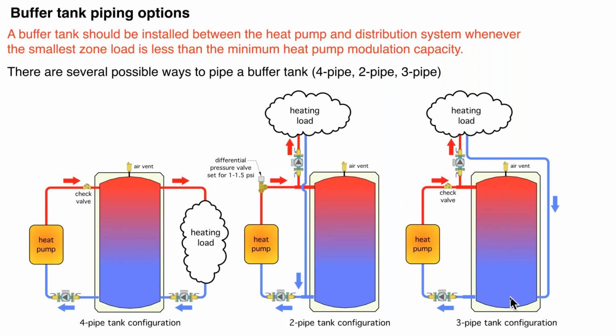But we're always assured that we're engaging the thermal mass of the tank, because all our return flow has to go through, in this case, the lower portion of the tank. And this can actually help with stratification as well, and it can help with keeping minimum water temperatures going back to that heat pump. And that's going to help ultimately the COP of the heat pump, to keep the water as cool as possible. If we fully mix these tanks, we're taking some of the warmer water at the top, and we're actually increasing the temperature near the bottom of the tank by blending these two together. And that's going to bring that water temperature up perhaps a few degrees Fahrenheit going to the heat pump. And from what we talked about last week, that is going to bring down both the coefficient of performance, and it's also going to slightly bring down the heating capacity.